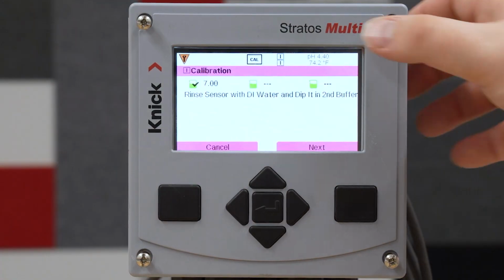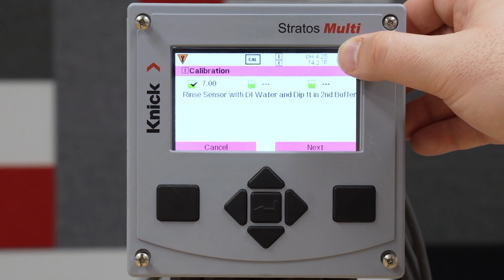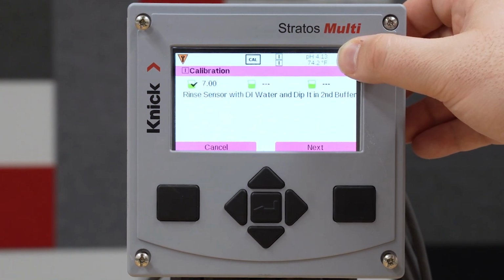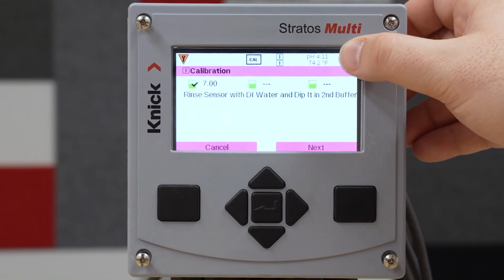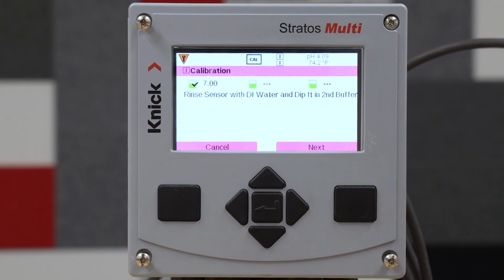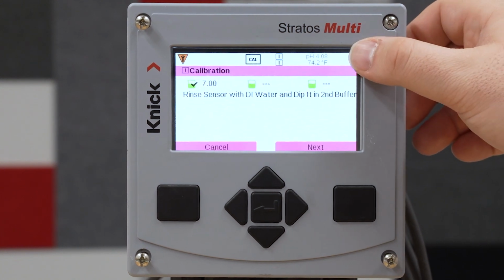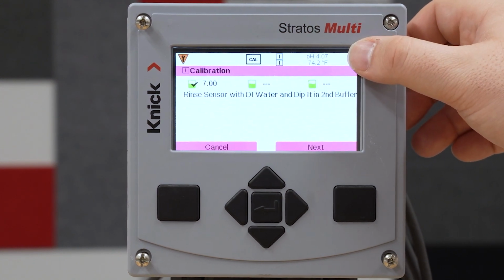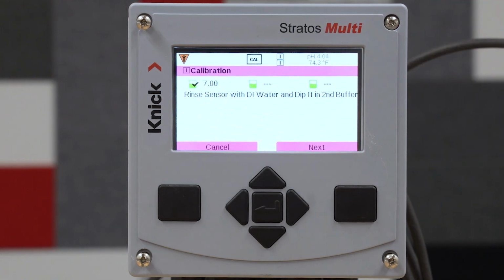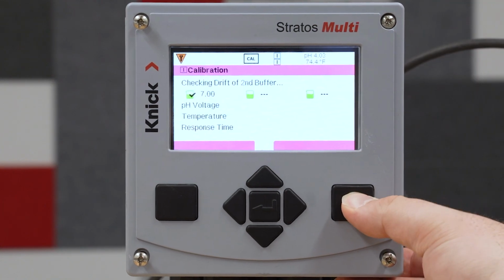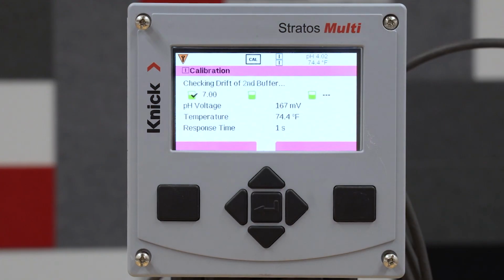Up here in the corner, you can see the pH value dropping to conform to the next buffer solution, which in this case is going to be the 4. You want to wait and let the sensor stabilize, let that pH reading stabilize so that you have a much better calibration. Press next. Again, the transmitter will register that the sensor is currently in the 4 buffer solution. Now you can move on to the last one.